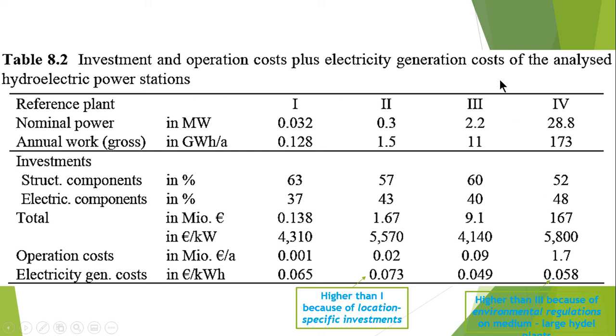Plant 3 is characterized by specific energy costs of around 0.049 euros per kilowatt hour and thus has the lowest specific cost for the generated kilowatt hour of electrical energy among the plants analyzed. On the other hand, the larger plant — plant number 4 — at 28.8 megawatt generates electricity at higher cost despite its higher full load hours.